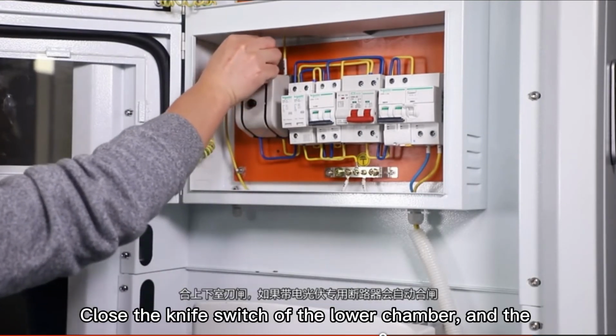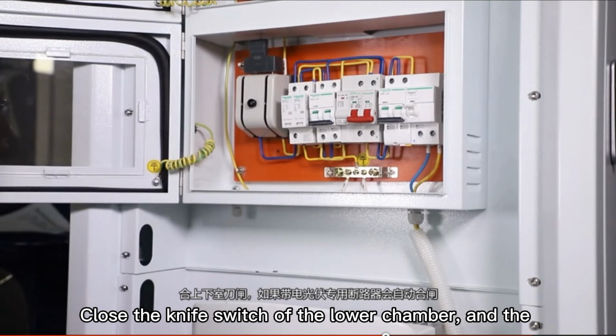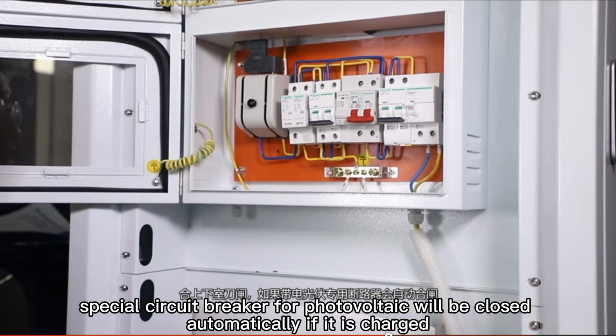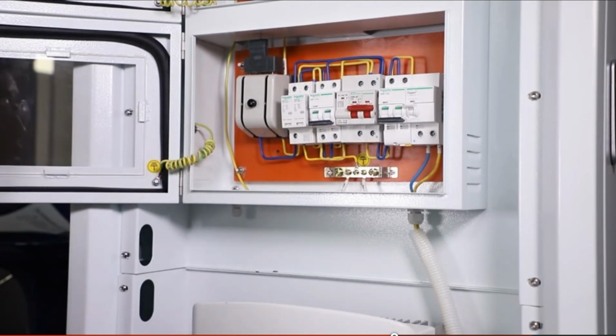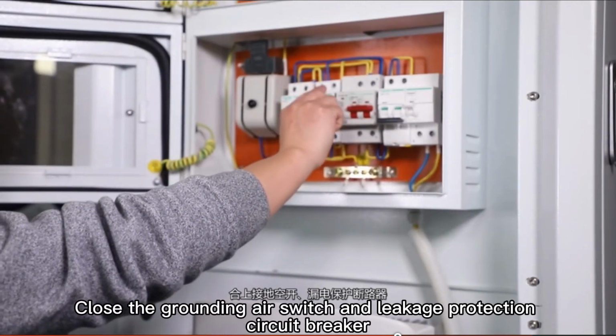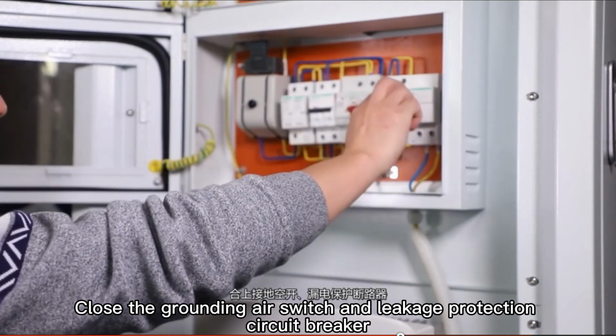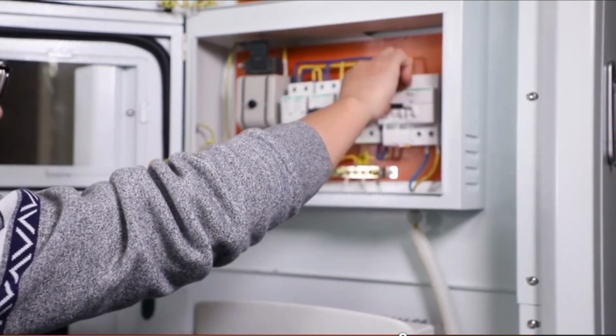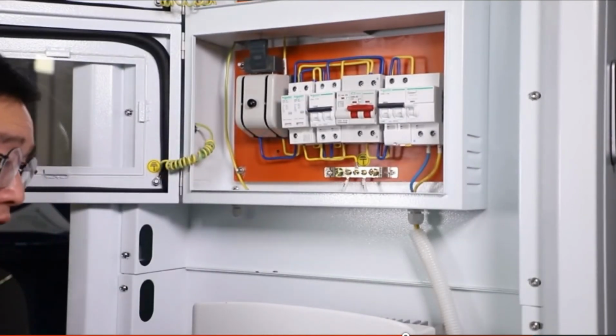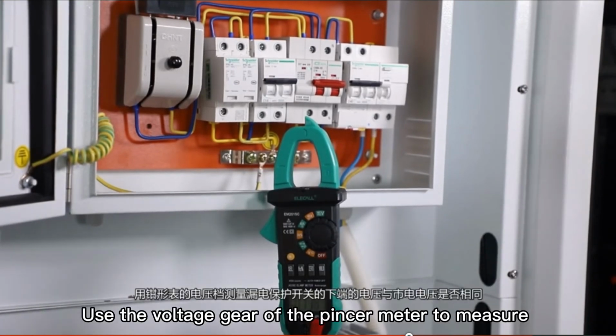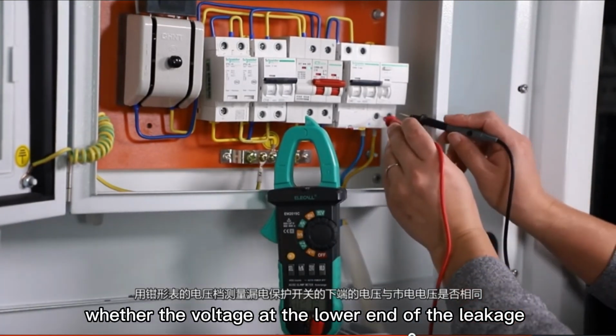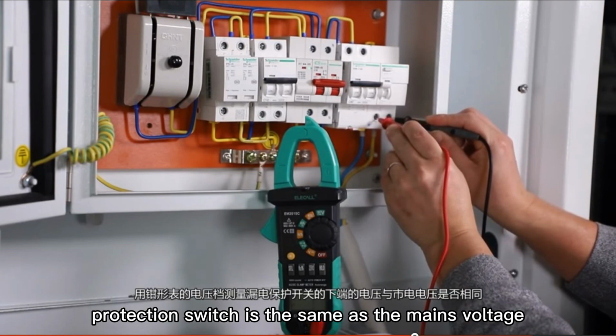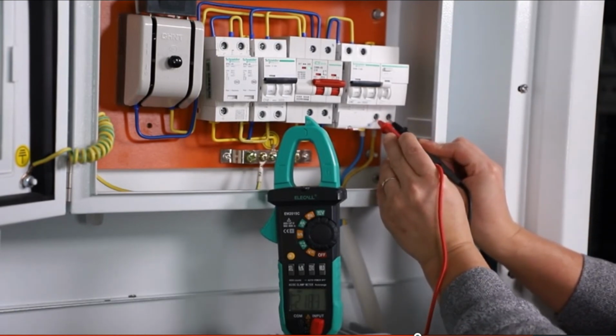Close the knife switch of the lower chamber, and the special circuit breaker for photovoltaic will be closed automatically if it is charged. Close the grounding air switch and leakage protection circuit breaker. Use the voltage gear of the clamp meter to measure whether the voltage at the lower end of the leakage protection switch is the same as the mains voltage.